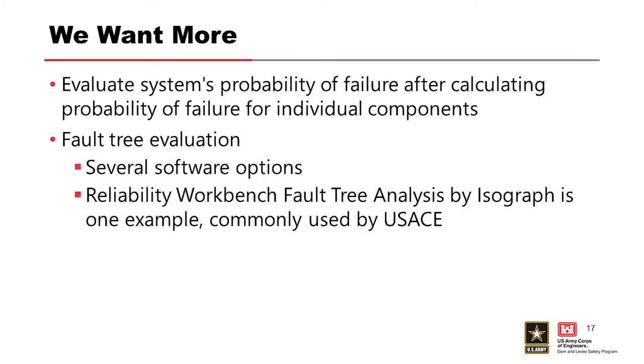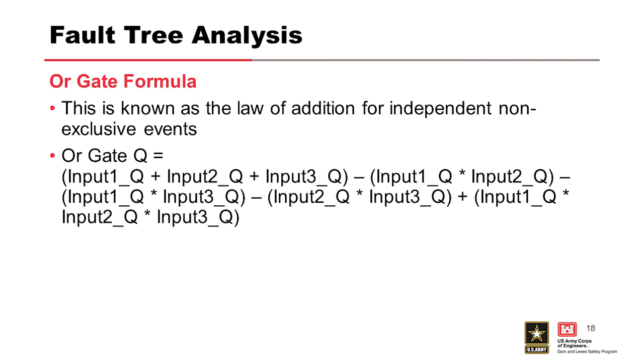So we want to know how to calculate a system's probability of failure. A system made up of multiple machinery components, so that typically involves for us, fault tree analysis. Fault tree analysis is made up of OR gates and AND gates typically for us, there are other type of gates.